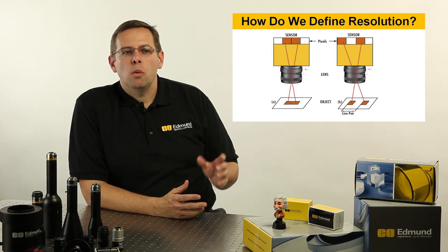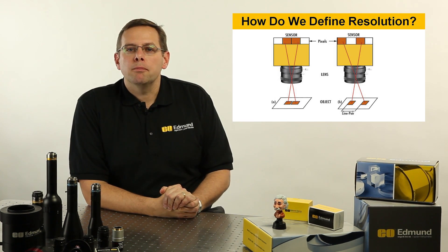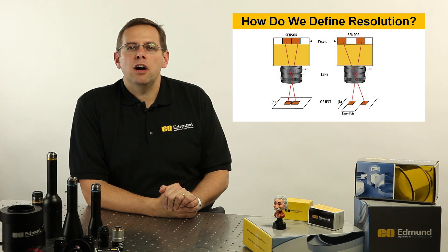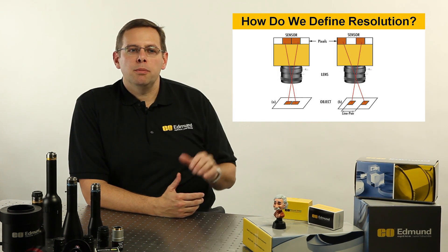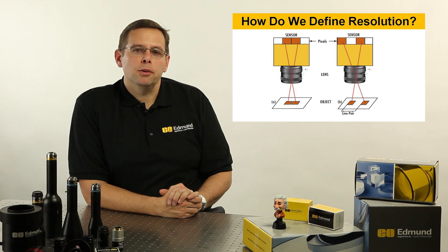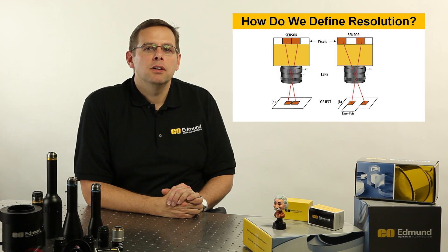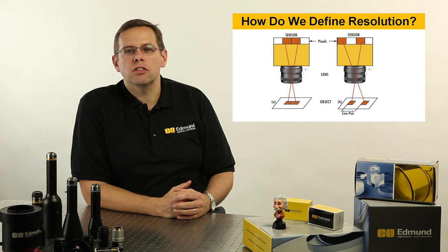Now let's put resolution into a real-world example. Imagine for a moment I have a piece of paper and I have a thousand spots on that piece of paper, and we have a camera system that has a thousand pixels in an array running along its length. If I was to image them, like we see in the example in part A on the slide, they would be imaged all adjacent to each other across that array of pixels. This would create a line that is one thousand pixels long — we would not see a thousand distinctive spots. So the limiting resolution, and the amount of parts we can actually break up the field into and see distinctive resolution features, is 500: one on, one off, alternating. That's about the limit that we can go to with the system.